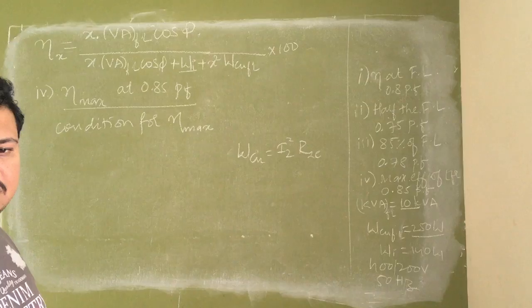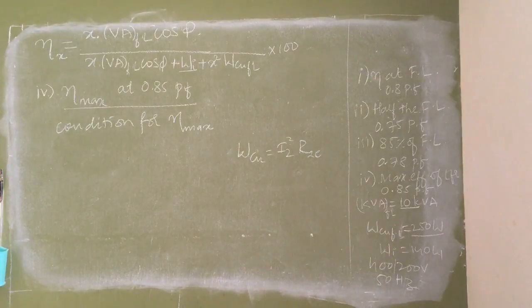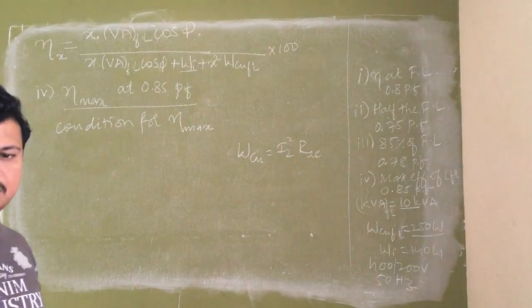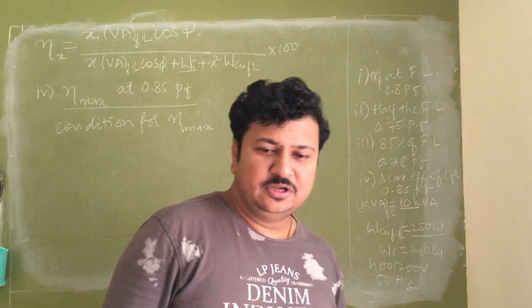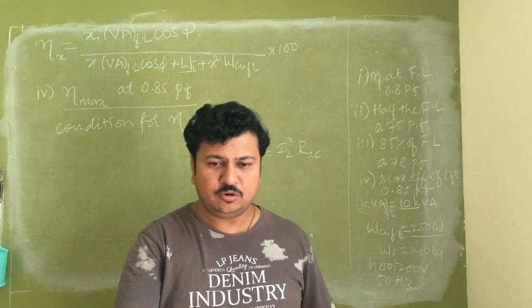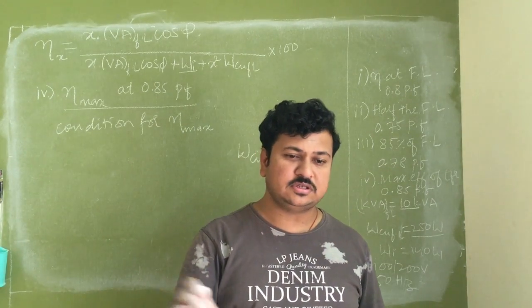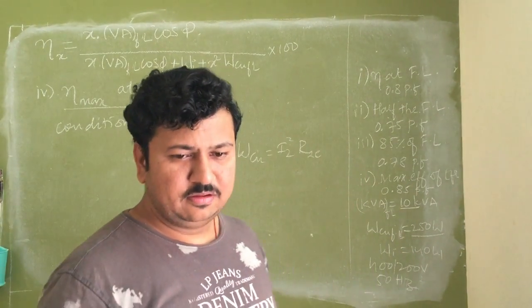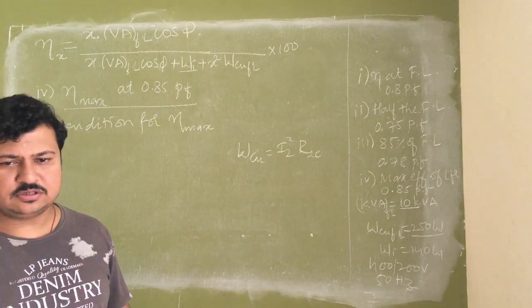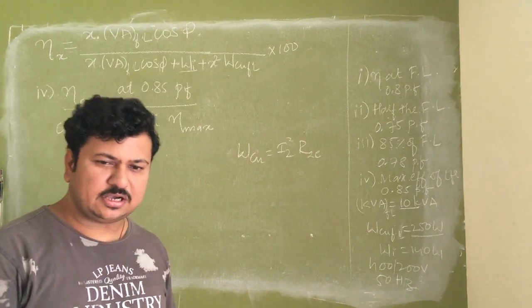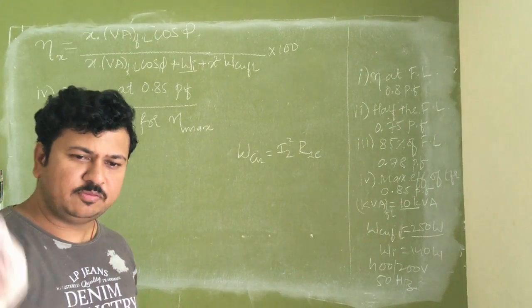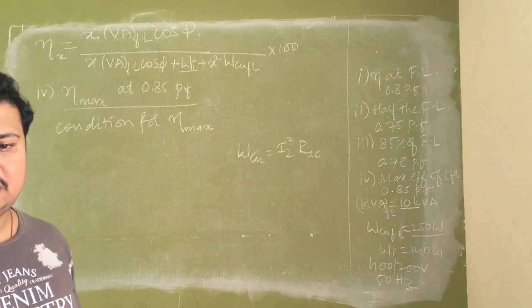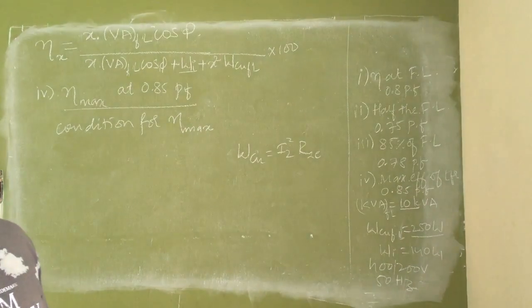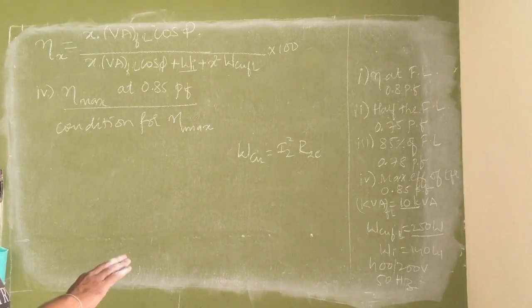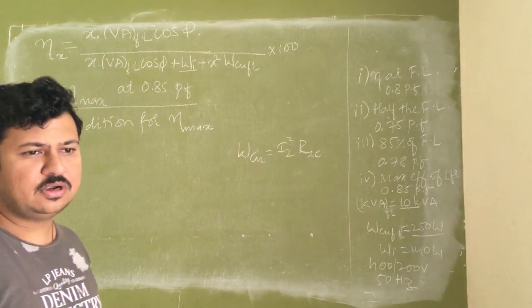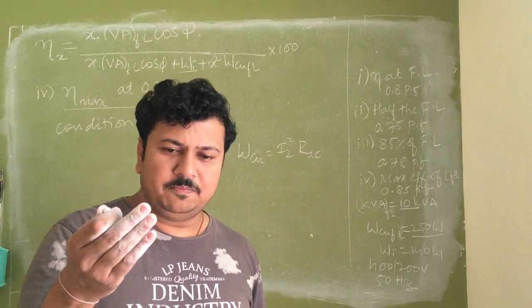If you take the other way, there is no meaning at all, because I cannot equate iron losses to copper losses, because copper losses are variable. So I cannot equate a constant to a variable, but I can equate a variable to a constant. I can write x equal to 2, but I cannot write 2 equal to x. It has got no meaning, though mathematically it is correct. LHS equal to RHS, hence proved, we write. But physically 2 equal to x has no meaning. So it is not only the mathematics we have to study, we should also understand the physical meaning behind that.